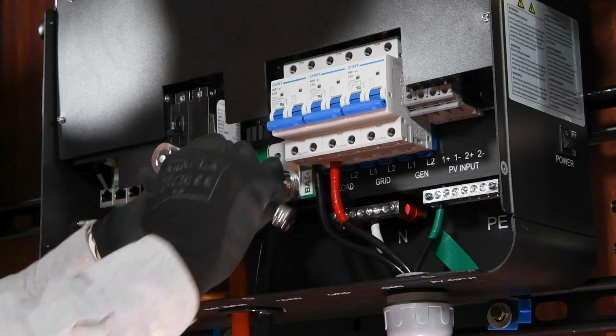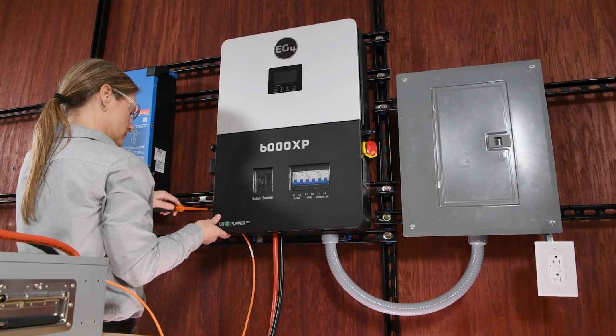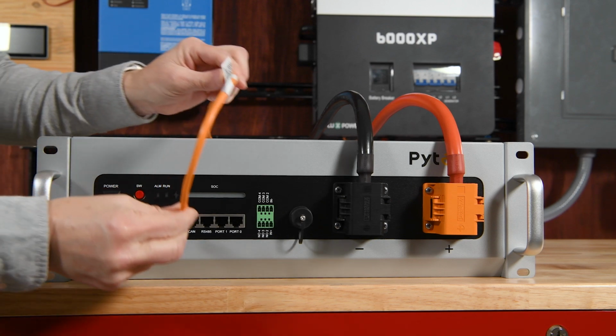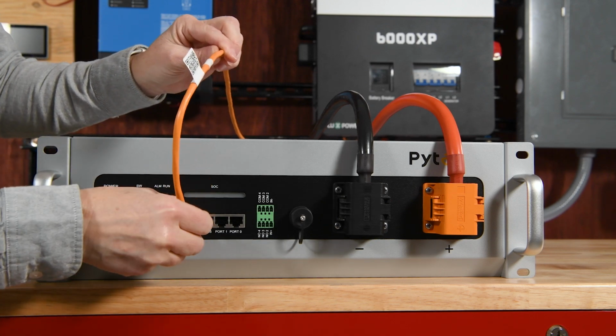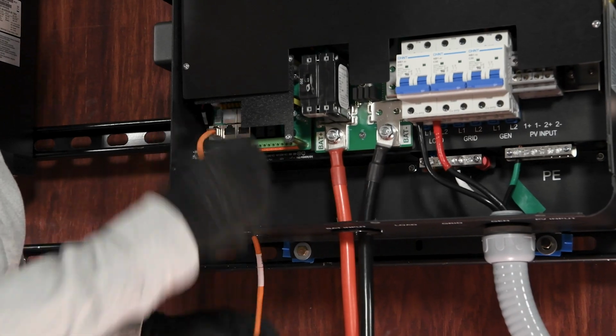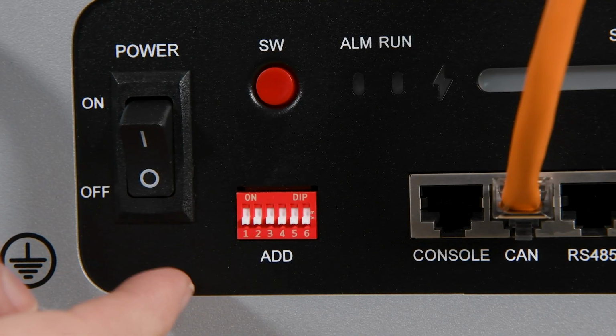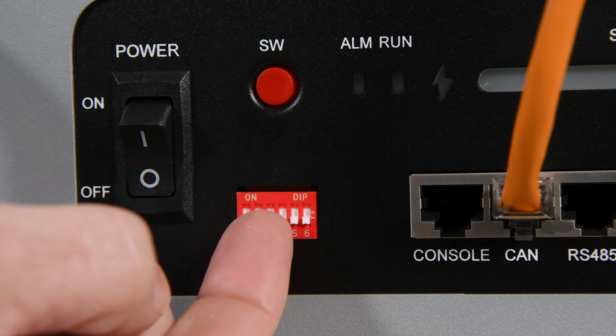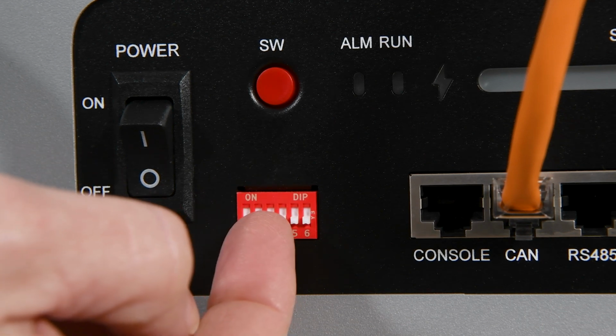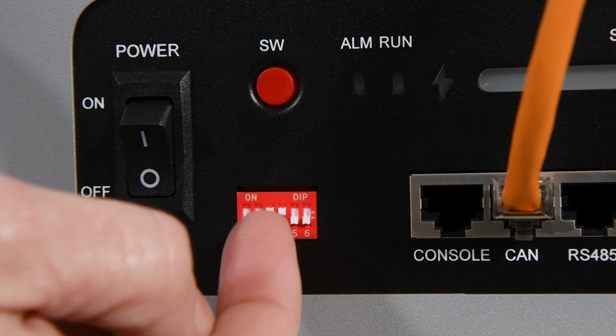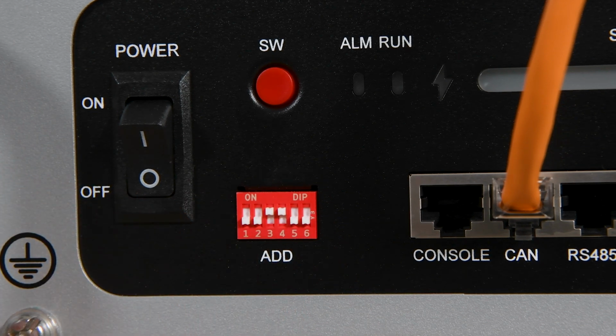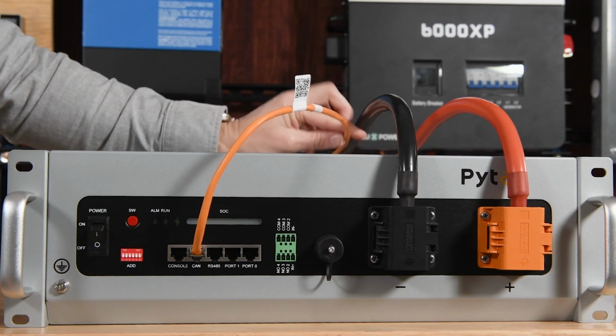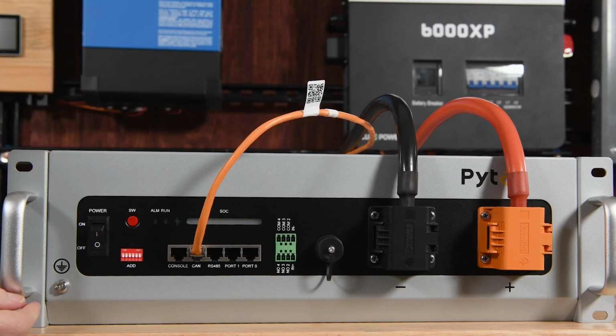We'll tighten the cables on both the battery and inverter terminals, making sure to double check polarity for safety. For the EG4 6000 XP, we're using CAN communication. We'll plug the communication cable into the CAN port on the battery and the COM port on the inverter. Next, we'll adjust the dip switches for the communication protocol. For EG4 or Lux Power inverters, switches 3 and 4 should be up, with all others down. With this setup complete, we're ready to power on the system.